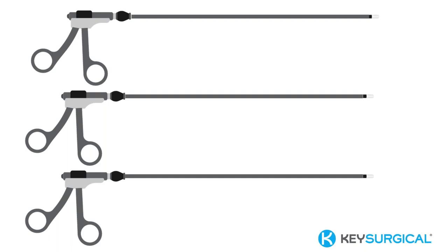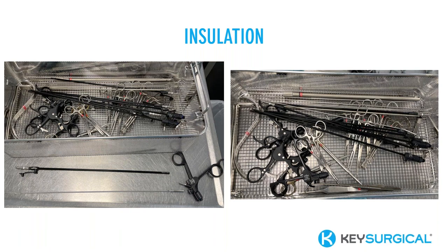So it's important to work with SPD and instrument manufacturers to know how to properly assemble the instruments before patient use. So here are some good examples from the facility I work at. Instruments are disassembled for decontamination, ready to be cleaned, then inspected on the pack and prep clean side with an insulation tester. Inspecting insulation is not just using an insulation tester. In sterile processing, the techs need to be trained to inspect during the decontamination process, as well as working with the instrument manufacturer to identify what to look for.